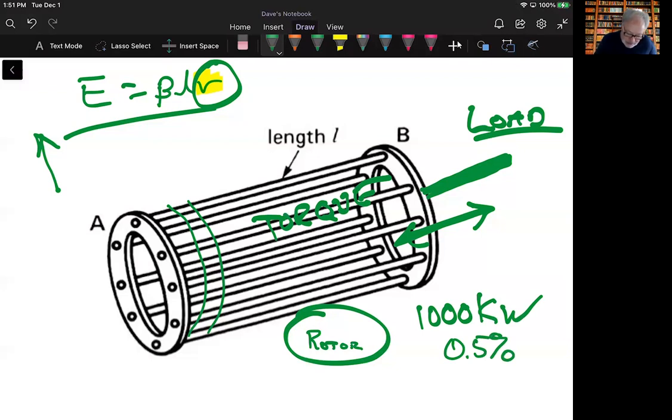Okay, so the slip, the difference between the magnetic field and the rotor field, is about 0.5% for large machines. And for smaller machines, like in the 10 kilowatt range, the slip seldom exceeds 5%, 5% difference.